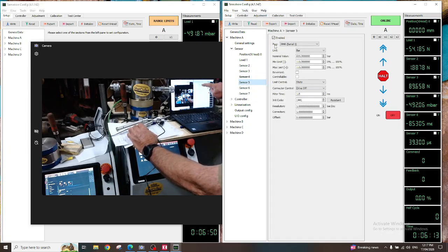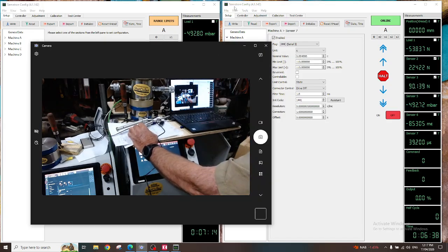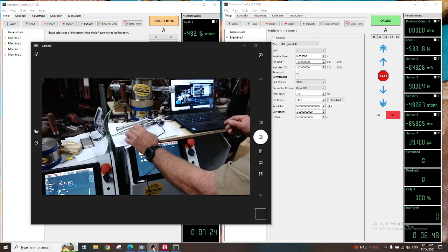Sensor 5 is a bar signal up to 600 bar coming from the confining pressure via a serial interface. 6 and 7 are the strain signals coming from the confining machine via serial cable. So that's how the data is being moved around. At this point, I'll stop the video and we'll come back to the next phase of the video in due course.